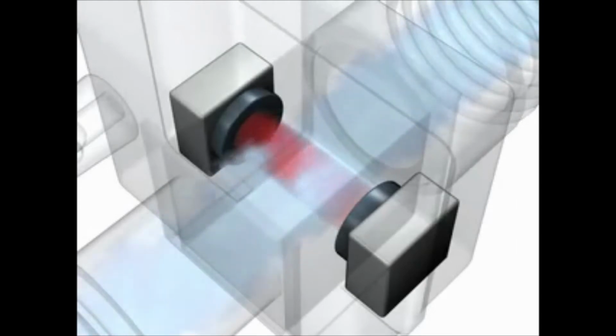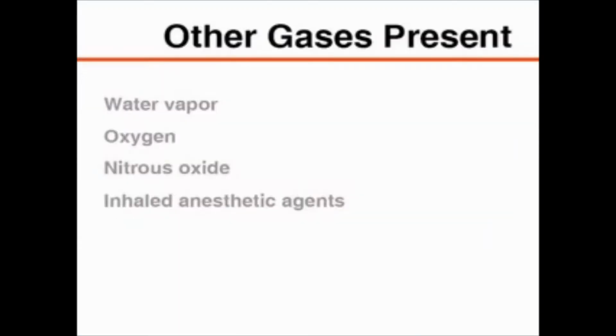Infrared light can be passed through a sample of gas to an infrared detector. As the concentration of carbon dioxide increases, the intensity of the light that reaches the detector decreases. Carbon dioxide gas strongly absorbs infrared light with a wavelength of 4.3 microns. At this wavelength, there is minimal interference from other gases that may also be present, such as water vapor, oxygen, nitrous oxide, and inhaled anesthetic agents.